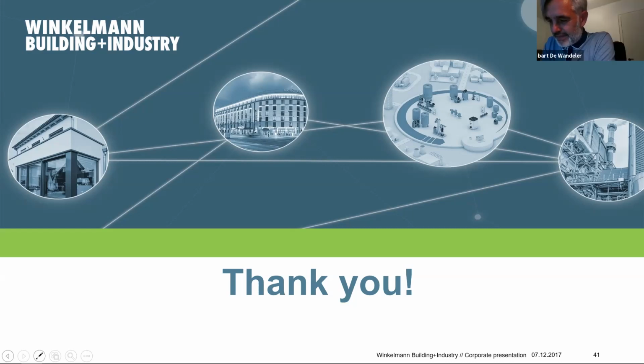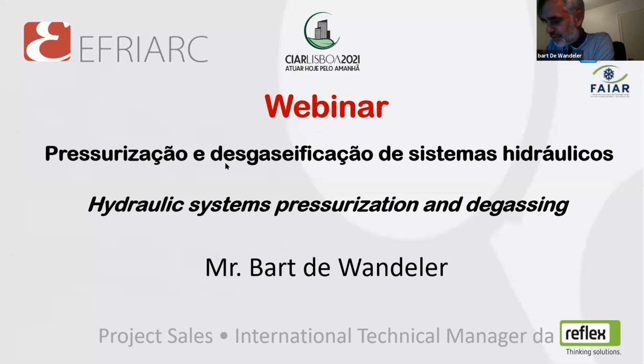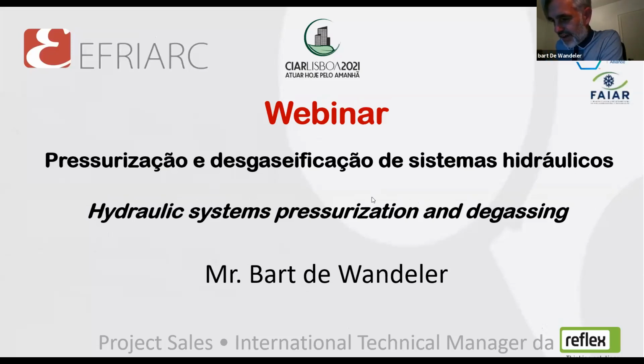Yeah, sometimes this is difficult. Of course we are limited. If you calculate a static expansion tank at a certain level, and the water volume in the system is too big, or the heating or cooling power is too high, then I would say disconnect the static option and don't calculate with a static vessel. On average, for systems starting around 200, 500, 700 kilowatts up to 1 megawatt, it would be good to calculate with a small Variomat, a small compressor, or a small pump instead of, for example, a static vessel.